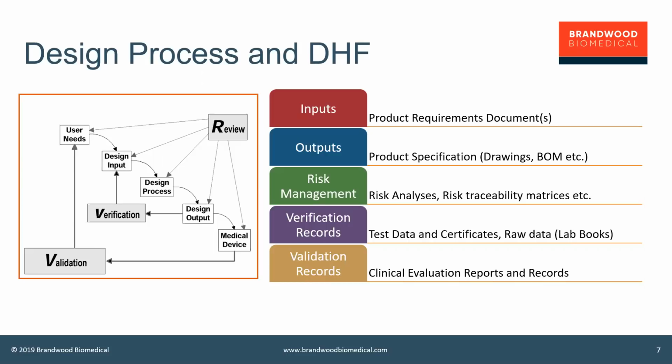Again, validation can include those clinical trials. It can include your CER, which may not have direct clinical trials, but may include an establishment against a comparative device. It may include your post-market surveillance. It also may include usability information. So that's how the design process and the DHF are kind of combined.